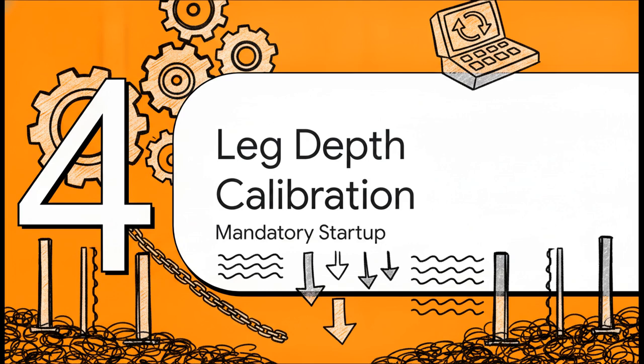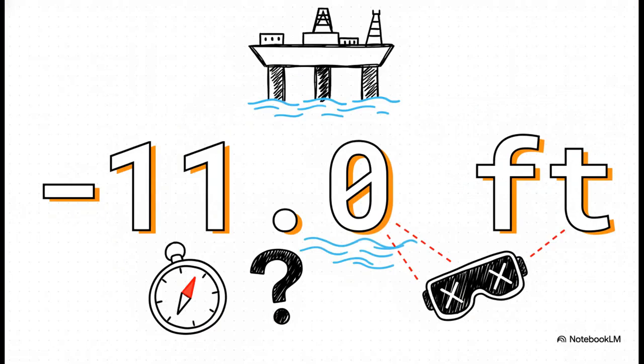This is your mandatory startup procedure. The short answer to what happens if you skip it: you are flying totally blind. Every single time the console powers up, you must perform a calibration. If you fail to do this after a PLC restart, the system just defaults to an uninitialized reading of minus 11.0 feet. The PLC has absolutely no idea where the legs actually are in the water, and that makes any jacking operation incredibly dangerous because your automated limits and uneven load detections simply won't function correctly.